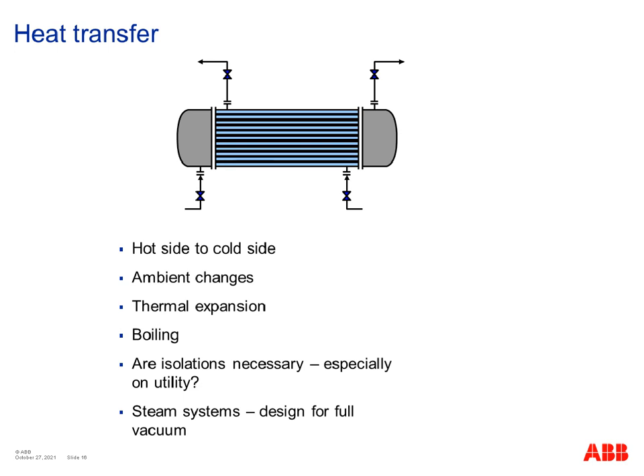So if you're worried about the cold side being overpressured from heat transfer, something you might want to think about is, do you actually need the isolations on the cold side? Because if you've got those isolations there, then you've got potential for the valves to be closed, and that could be done inadvertently by an operator error or anything like that. So if you were to design out those valves and just not have them there, then there's no way for that to happen, and it wouldn't be possible to block the cold side in, so you could actually eliminate the relief case in that way. So always just ask yourself that question: do you really need those isolation valves?